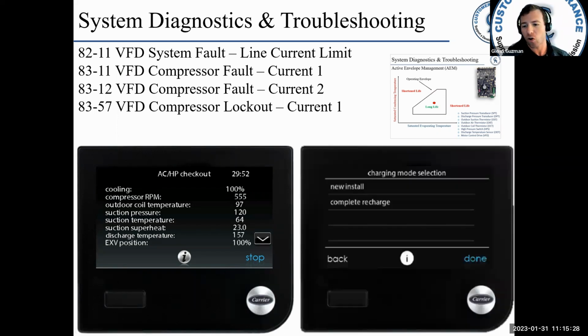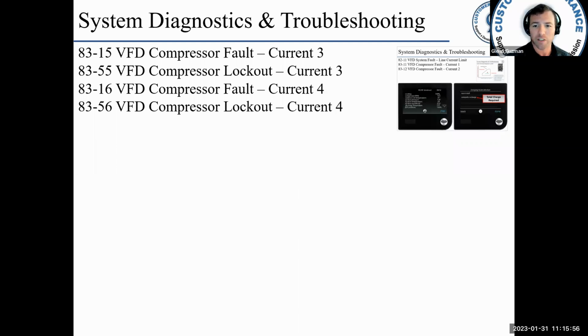If you're getting these current faults, then what causes the compressor to draw high current? Right, overcharge, high condensing pressure, that sort of thing. You may need to do a complete recharge: recover the gas, evacuate and recharge it. That could be an issue there, causing a high current. Okay, 8315, 8355, there's your current 3, and 8316, 8356 is your current 4.